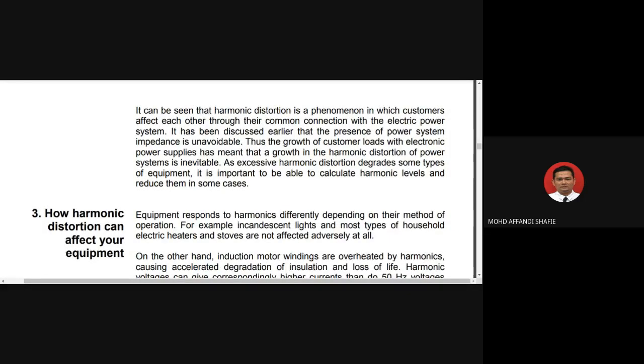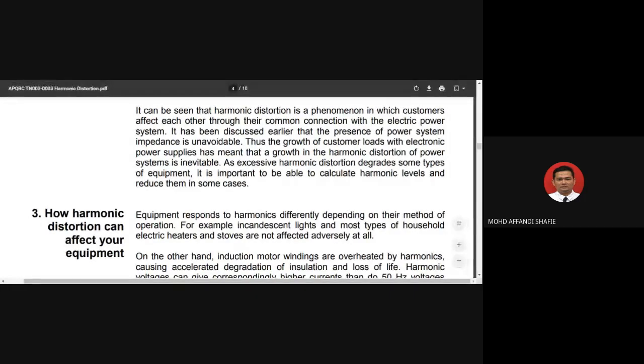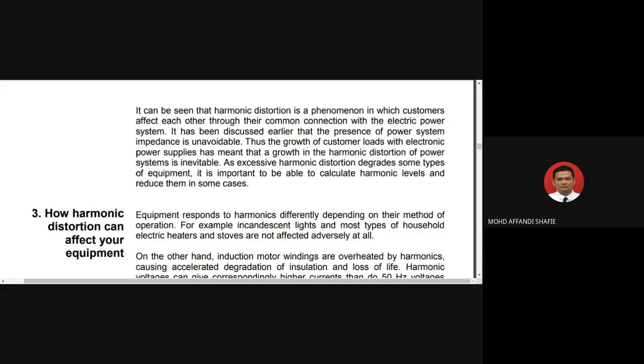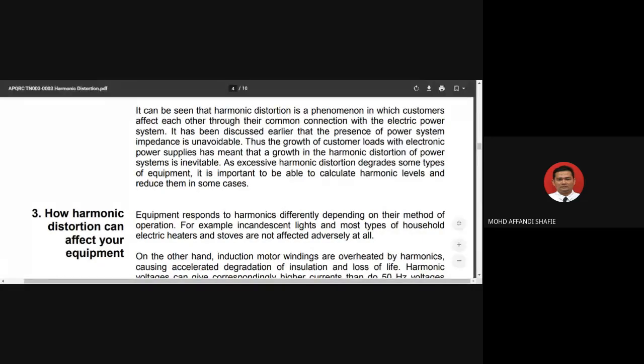So it can be seen that harmonic distortion is a phenomenon in which customers affect each other through the common connection with the electric power system. It has been discussed earlier that the presence of harmonics in a system is unavoidable, given the growth of customer load. Okay, so this term is important. Thus the growth of customer load with electronic power supply has meant that growth in the harmonic distortion of power systems is inevitable. So as excessive harmonic distortion degrades some types of equipment, it is important to be able to calculate harmonic levels and reduce them in some cases.